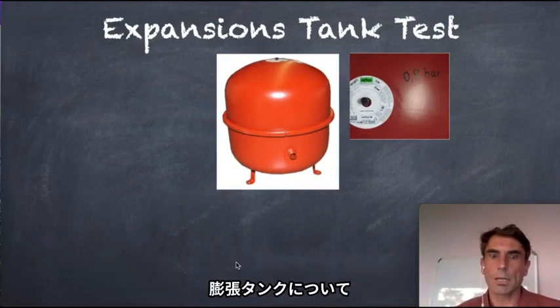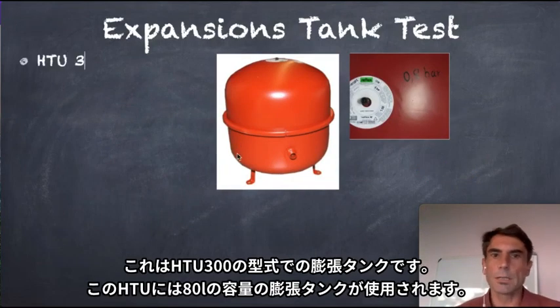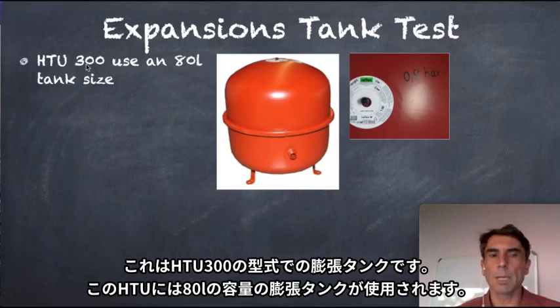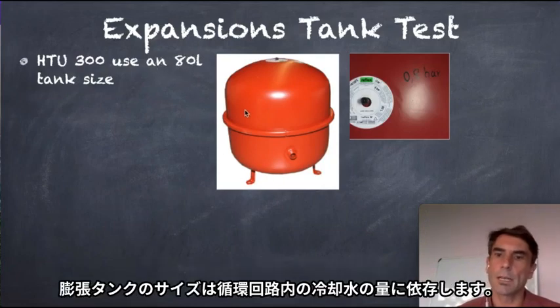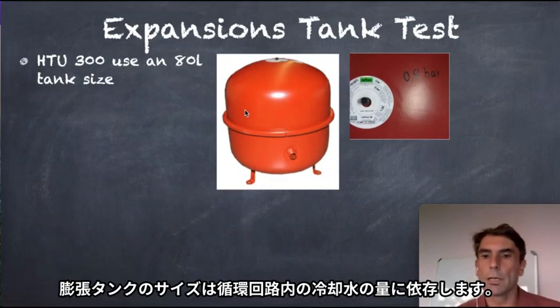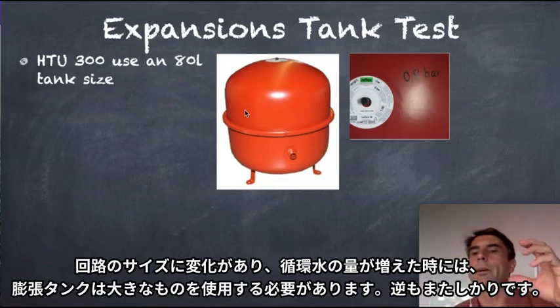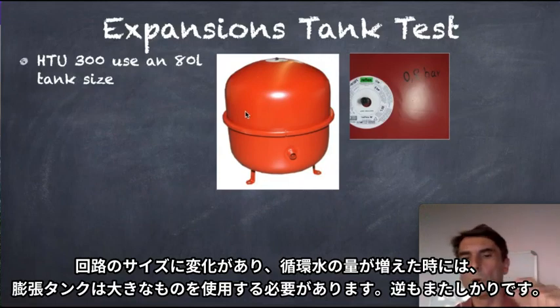That's the expansion tank. So you get the expansion tank in different volume sizes. This is the expansion tank for the HTU 300. There we use 80 liters. So the size of that tank depends on the volume of water in this cycle. If you have a different cycle with more water, you need a bigger expansion tank. If you have a cycle with less water, you need a smaller expansion tank.